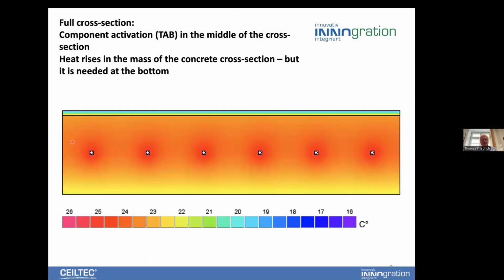You see here the traditional one with a very big, full cross section. You put the tubes in the middle, and then you heat it, and you can see the heat goes up into the upper part, but it is needed at the lower part. We have the thermal storage, but we also need the comfort to bring the energy into the room, and you see here it is not fully possible - it takes time to bring the energy from the cross section to the surface of the ceiling.